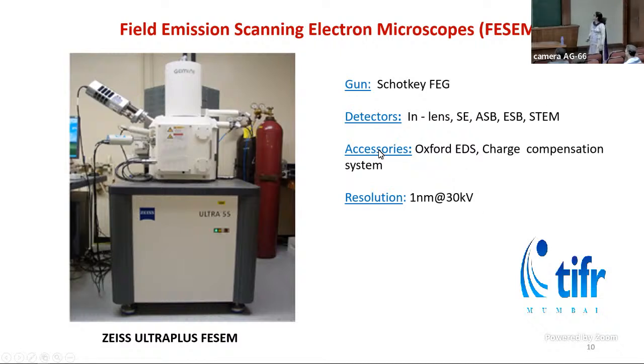Now, why is a charge compensation system needed? Earlier, I mentioned that we need conducting samples to be imaged with SEM. So what happens is when this electron beam hits the sample, if the secondary electrons emitted from the sample are not grounded properly, it creates an electron cloud over the sample. And that electron cloud deflects the primary beam, resulting in movement of the image, or some portions of the image getting dark, or some portions getting excessively bright.